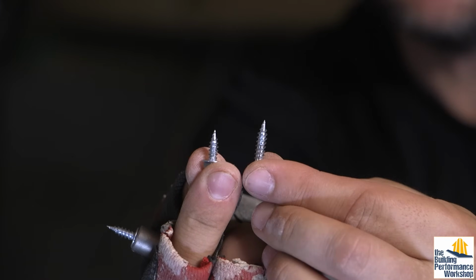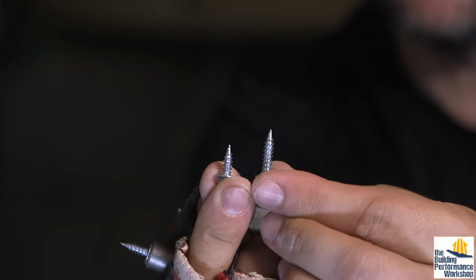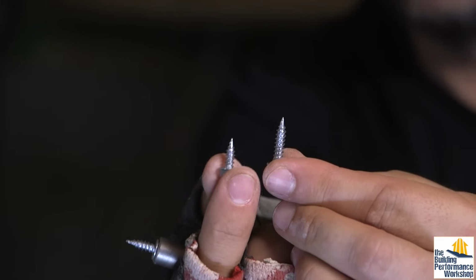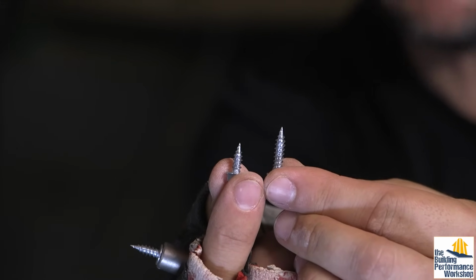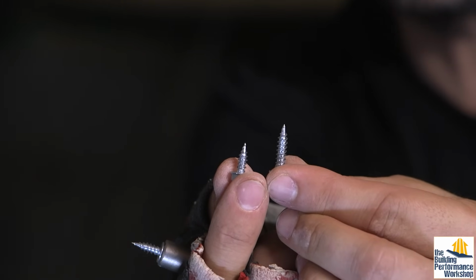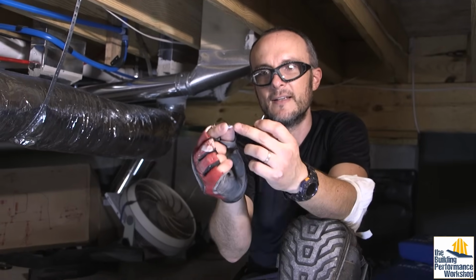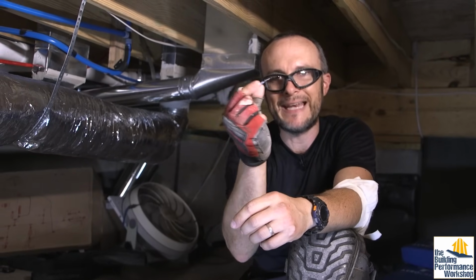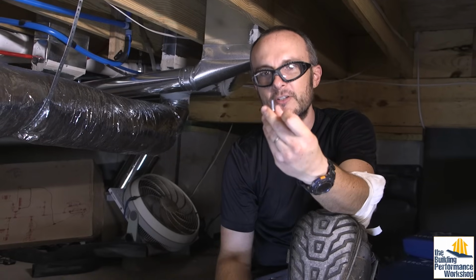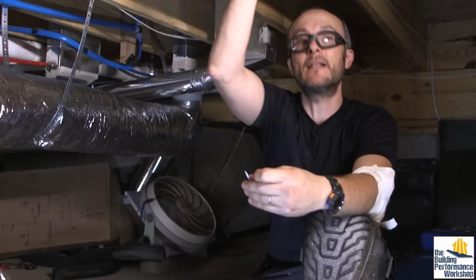The little guy is a 3/8, and the big one is a 3/4 inch screw. I'm using the 3/8 mostly for the ducts themselves, and then I'm using the 3/4 inch sometimes for heavy portions of ductwork where you're trying to sandwich together a lot of different pieces of metal, and it's hard to get this thing through because you need it to really bite into every single layer. So that's what these are good for, but these are also really good for screwing into wood.